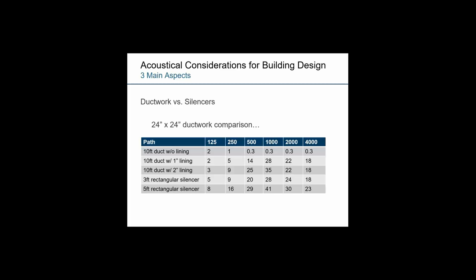As you add something like a duct liner, you typically see a higher level of sound absorption, and a 1-inch liner versus a 2-inch liner yields even further benefit. Silencers typically have acoustic media contained within them to help absorb that sound energy present within a ducted system. As sound transmits through a silencer, that sound energy is converted and absorbed in the baffles to reduce the transmission of sound through it. And you can see a silencer can have quite high insertion loss values at maybe a lower length. A 3-foot or a 5-foot silencer can absorb and attenuate quite broadband attenuation in all frequencies.